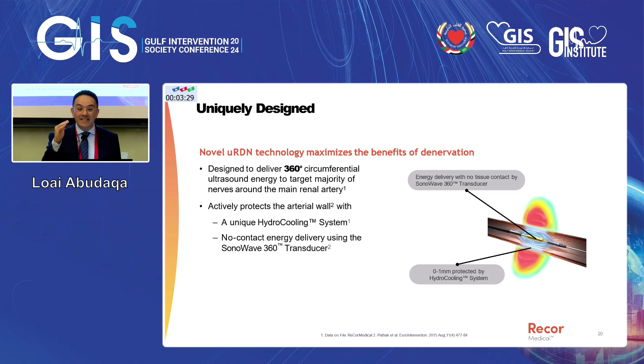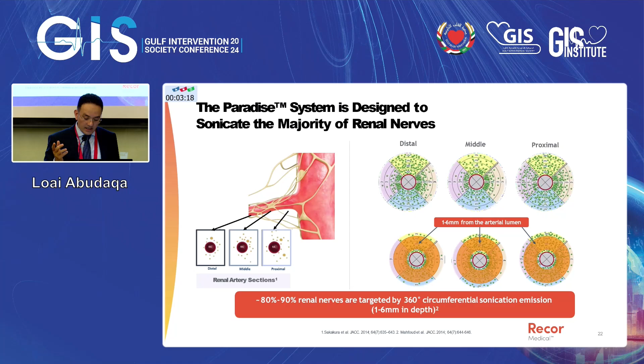This hydrocooling system depends on water. When you start ablations, there will be no direct contact of the transducer with the wall, so less damage to the wall. Again, approximately 80 to 90% of the renal nerves are targeted with the 360-degree circumferential sonication emissions, which covers the depth of the renal nerves, which I told you before.